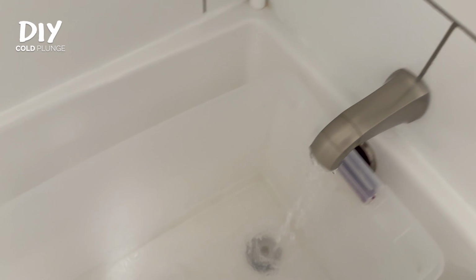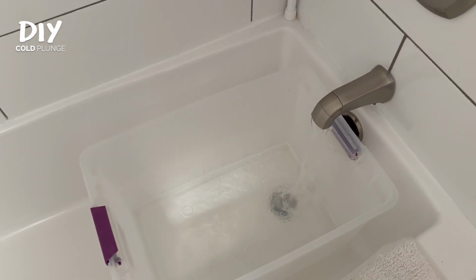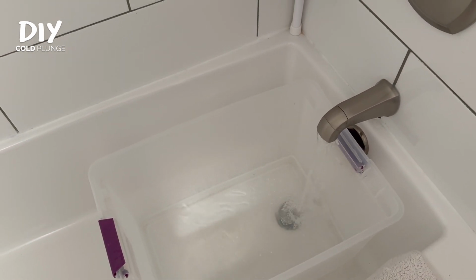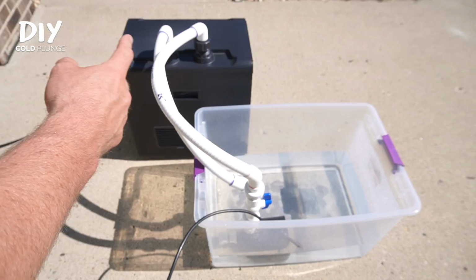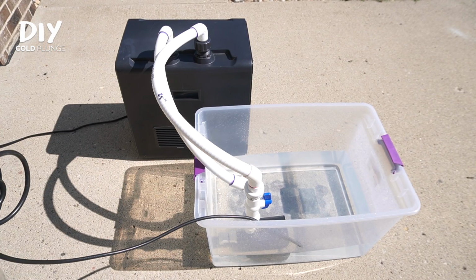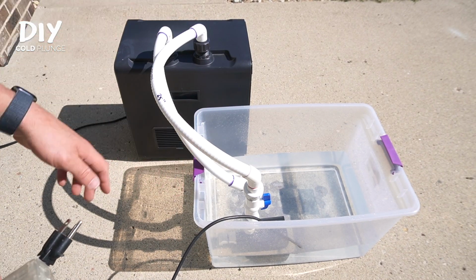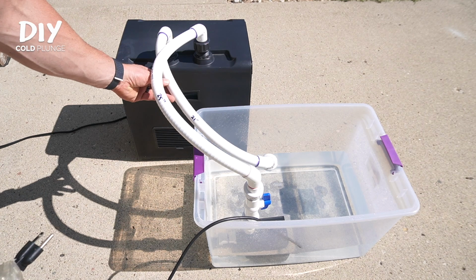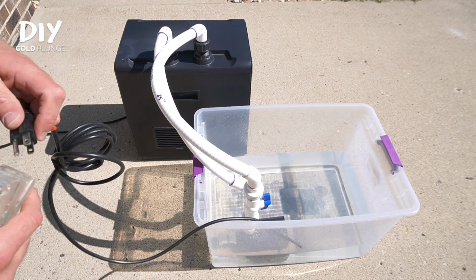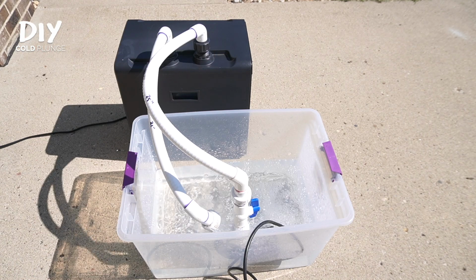Next, it's a good idea to flush out the inside of the chiller. To start, fill a bucket or tub with warm water. The cool thing about how we set up the plan is that you'll be able to use all of your components to clean this out. You'll hook your pump up to the in port on your chiller like you normally would, detach your out port and feed that back into the bucket or tub you're using, then plug the pump in and start going.